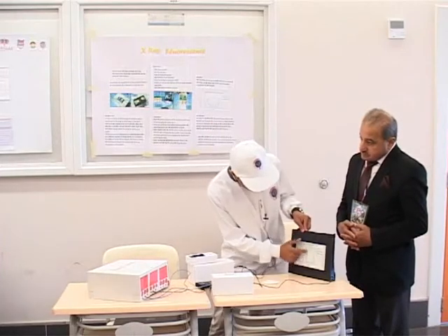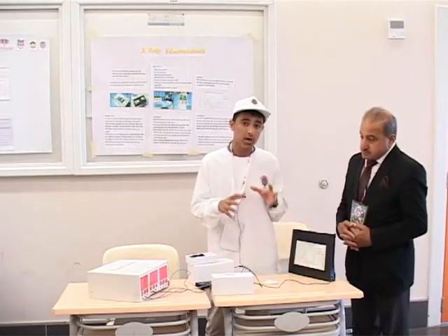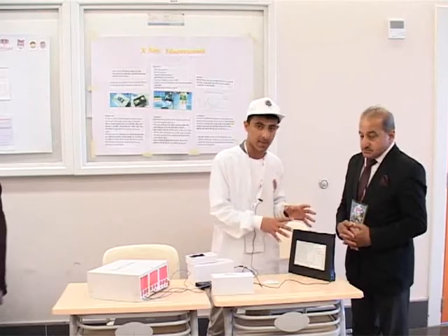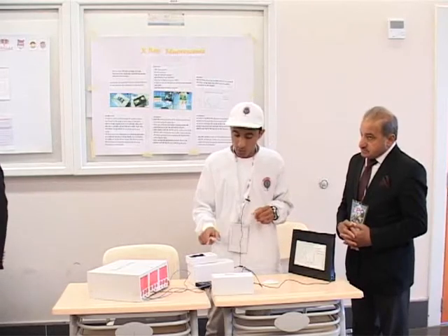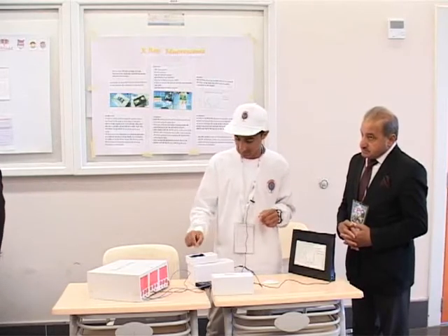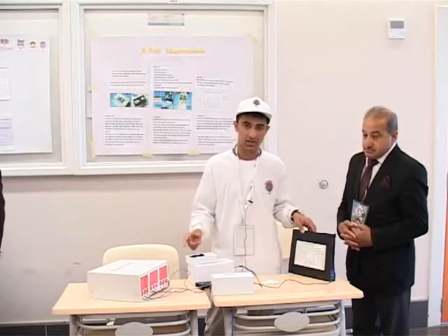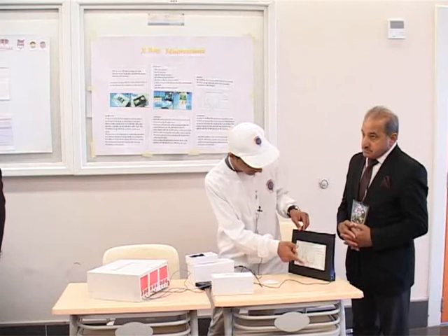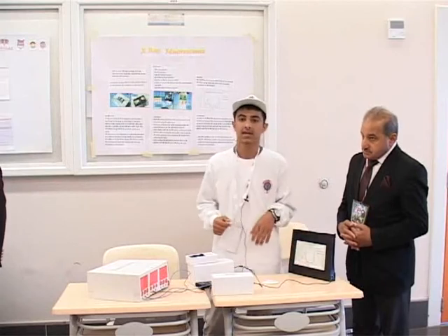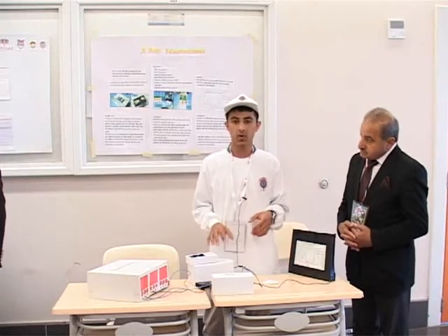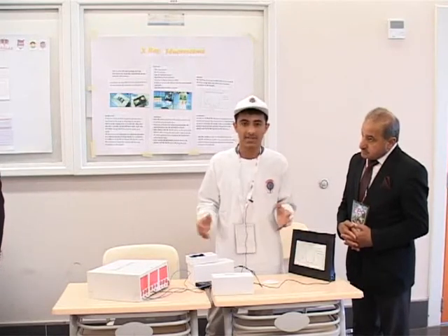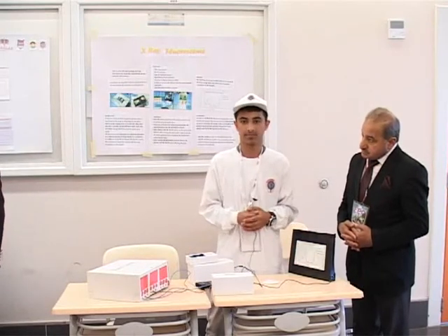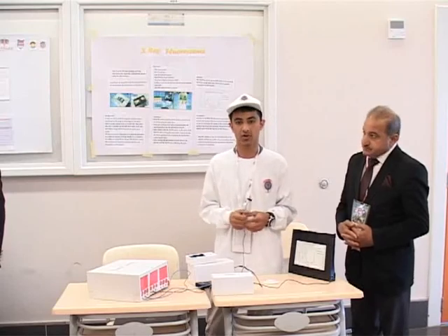The ADC will send it to the computer and it will produce peaks for that unknown material. When we determine these peaks and compare them with a database in the computer, we will know that this sample is gadolinium according to these peaks. In this way, we can determine any unknown sample in the lab using X-ray fluorescence.